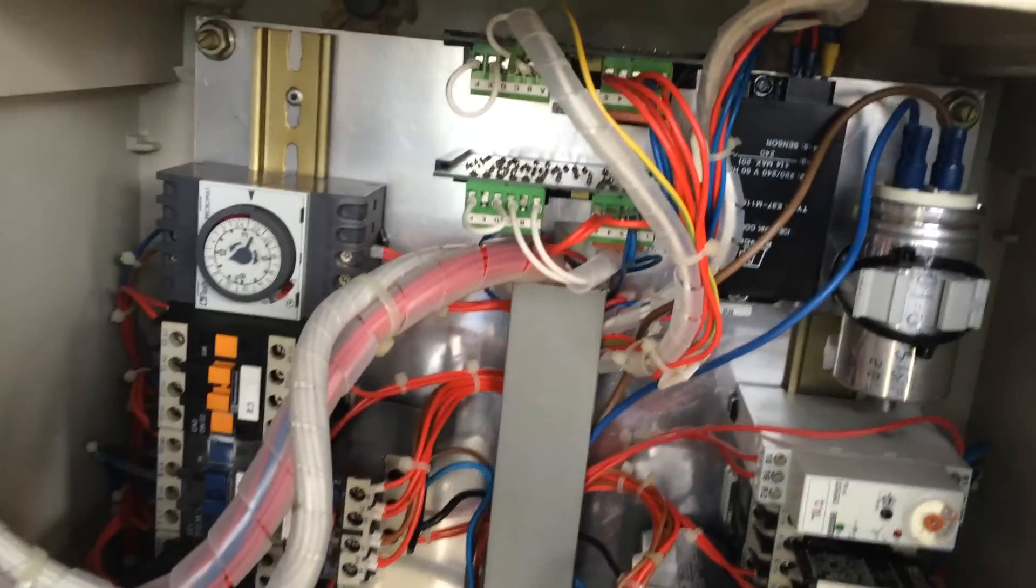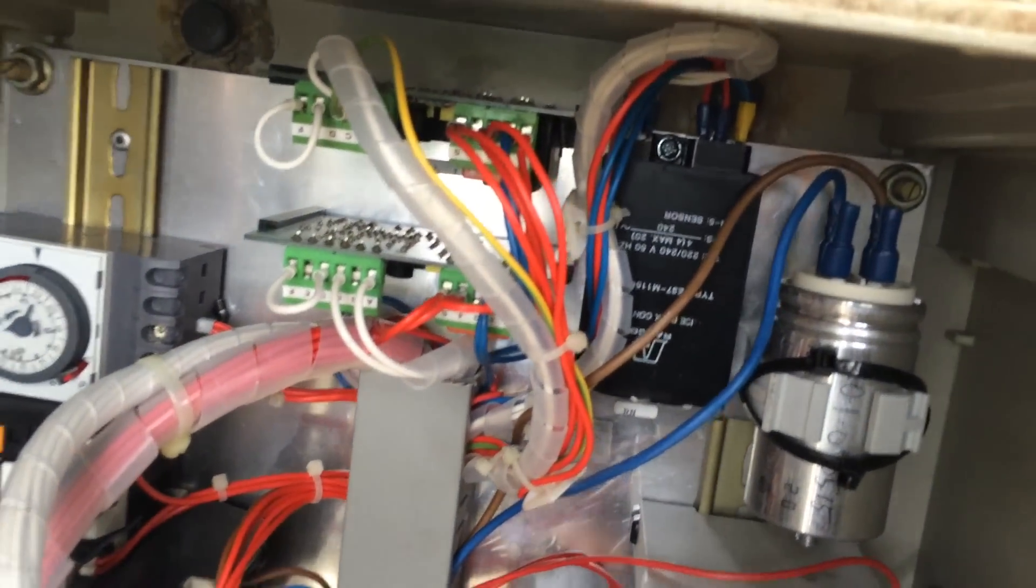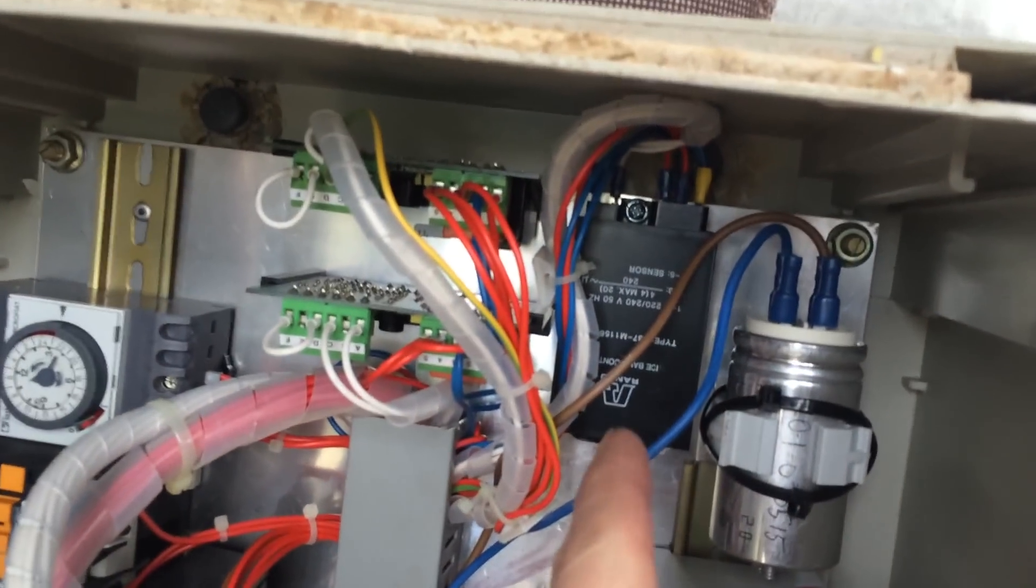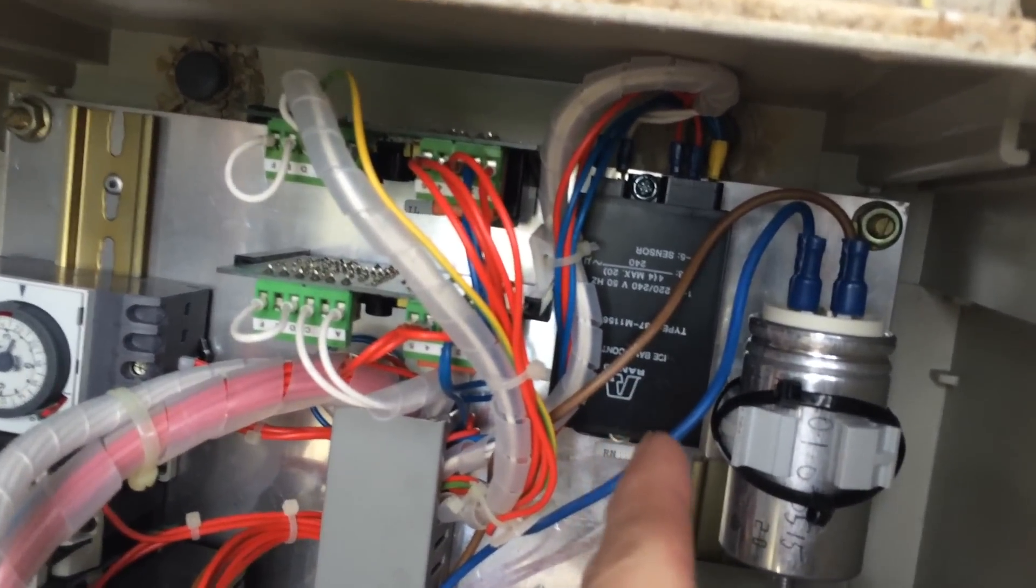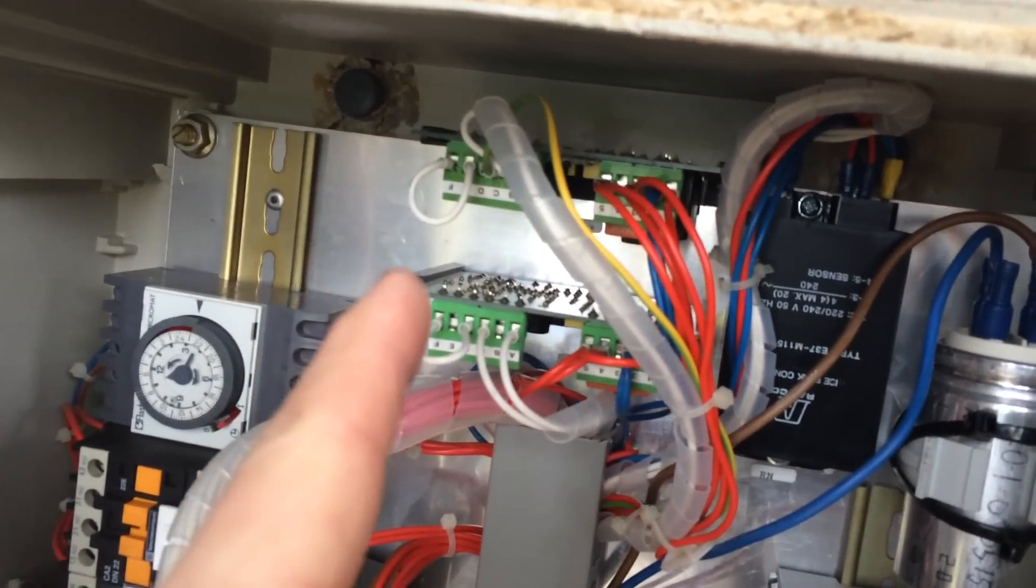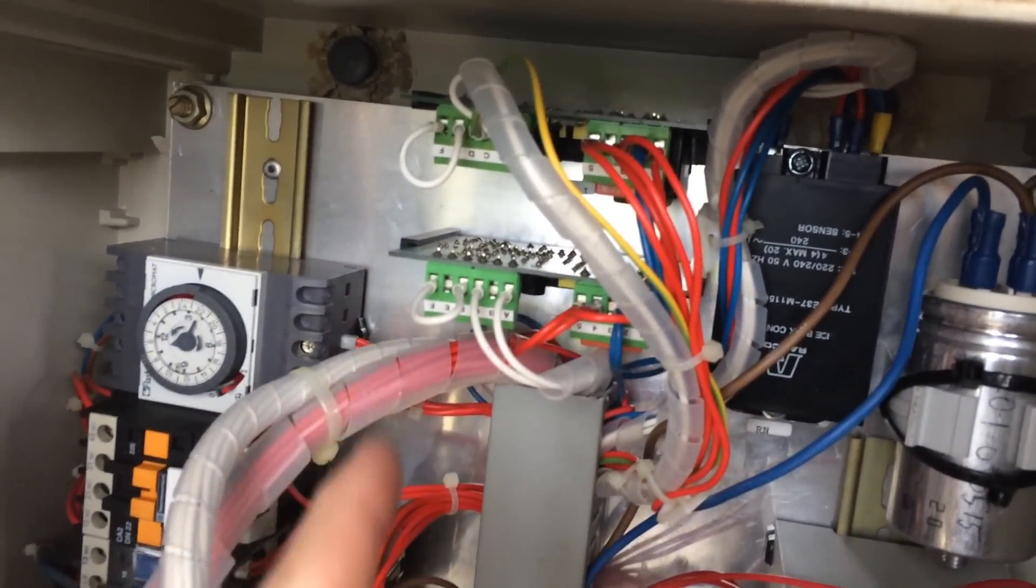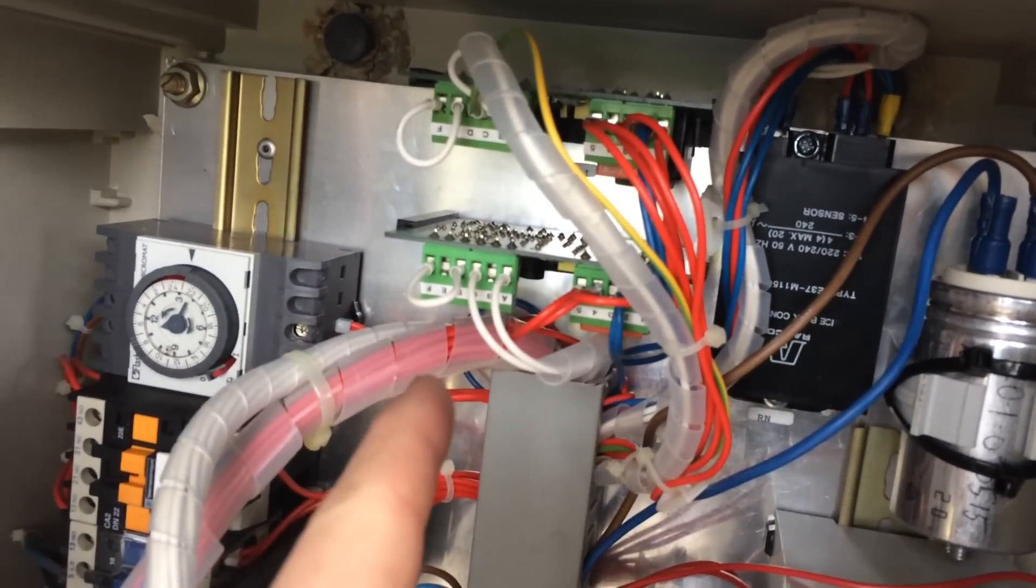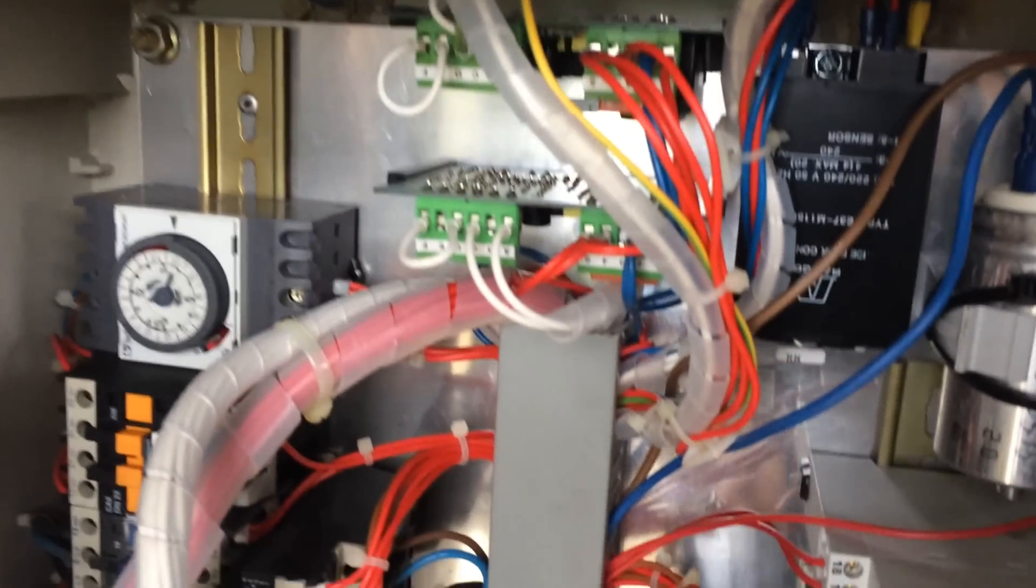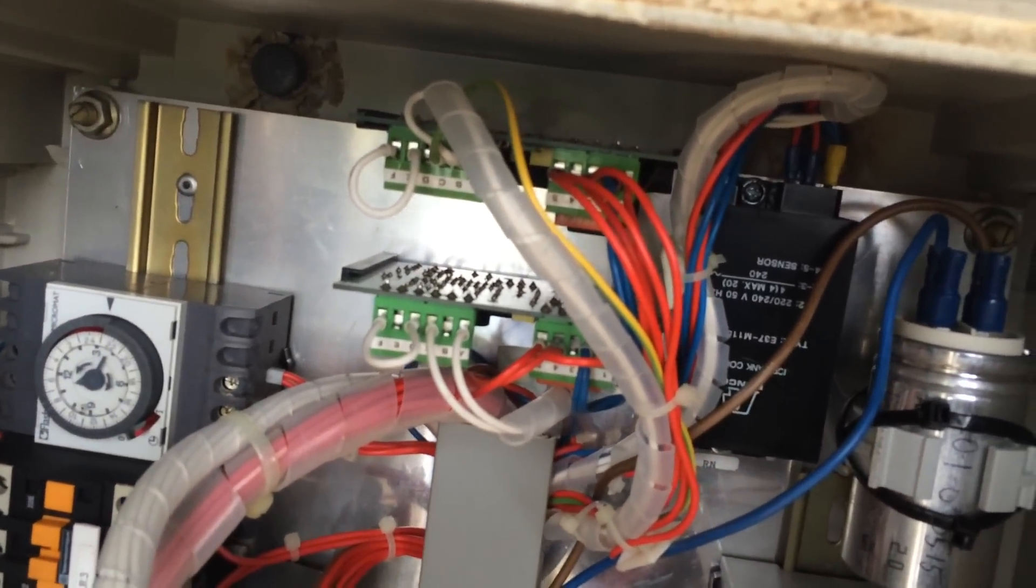This is the control box. We've got two ice bank controls. We've replaced one with that Ranco one there. One of these other ones is the other ice bank control, and the third one is used as a level sensor for the water filling in the wash. I have had those play up in the past.